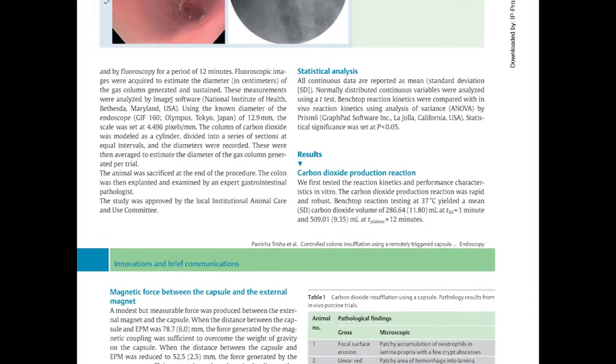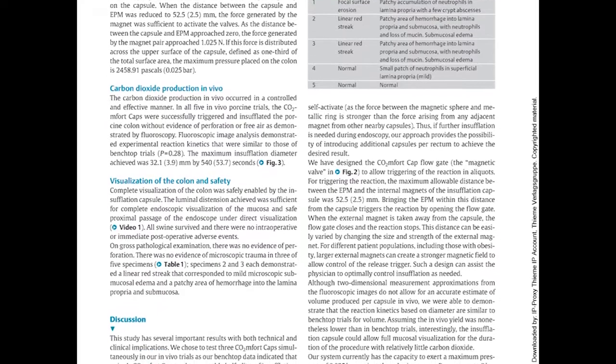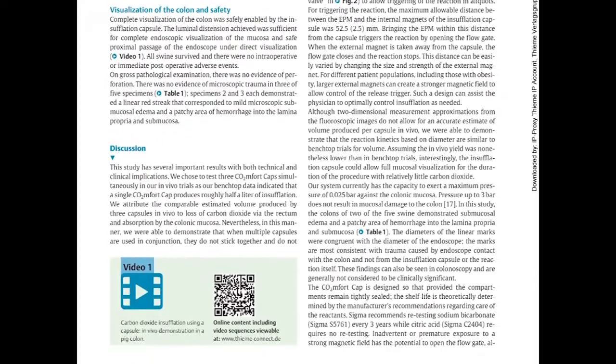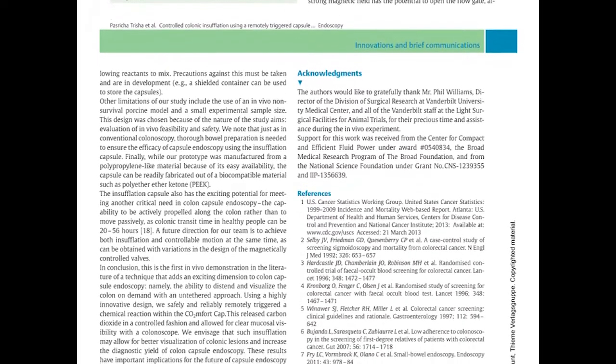In this study, we examined the feasibility and safety of this device in vivo. We demonstrated that CO2 production in vivo occurred in a controlled and effective manner. In all five in vivo porcine trials, the CO2mfort Caps were successfully triggered and insufflated the porcine colon without evidence of perforation or free air demonstrated by fluoroscopy. The lumen distension achieved was sufficient for complete endoscopic visualization of the mucosa and safe proximal passage of the endoscope under direct visualization.